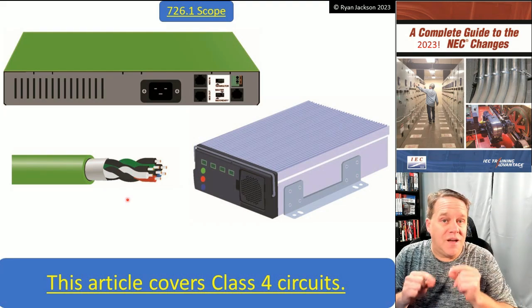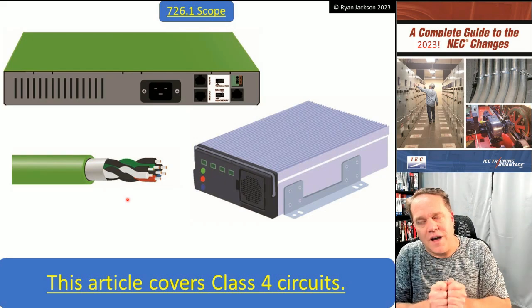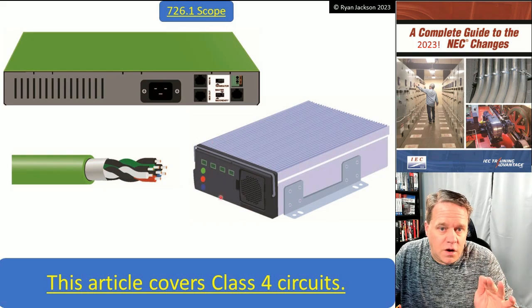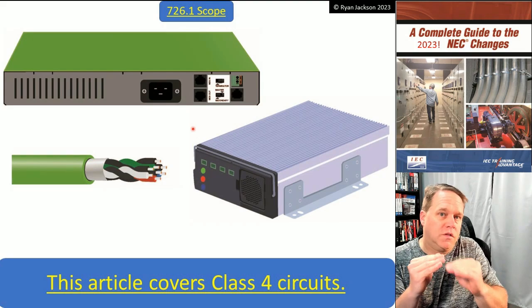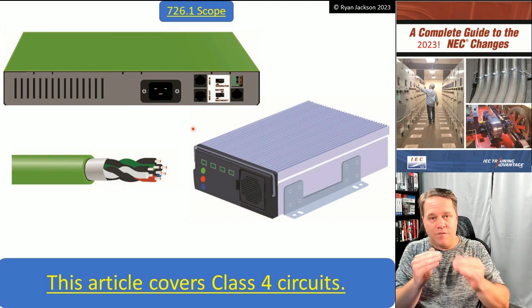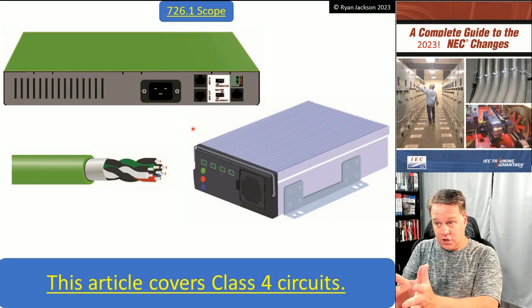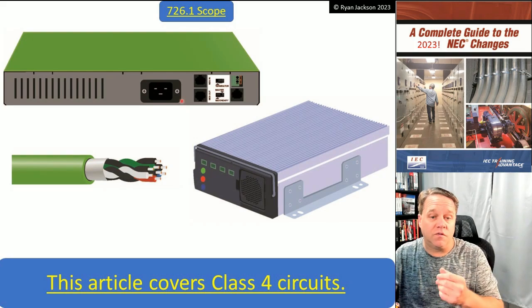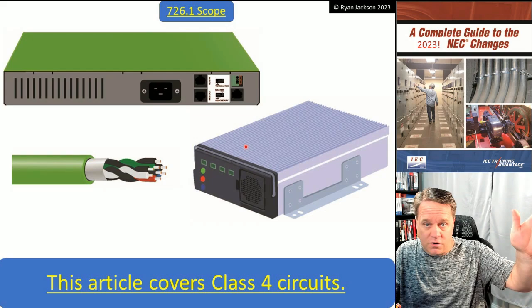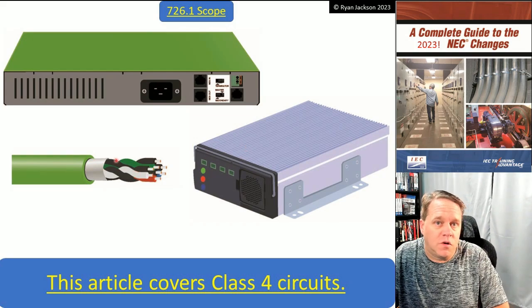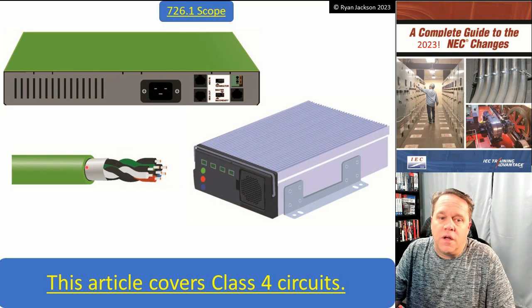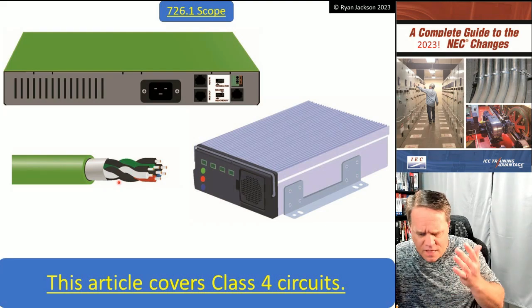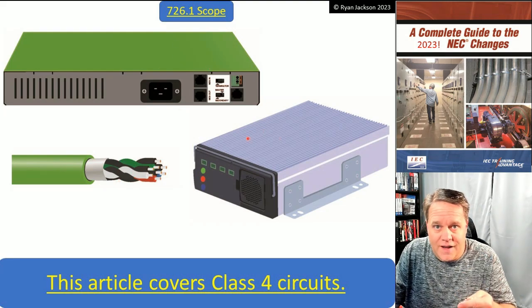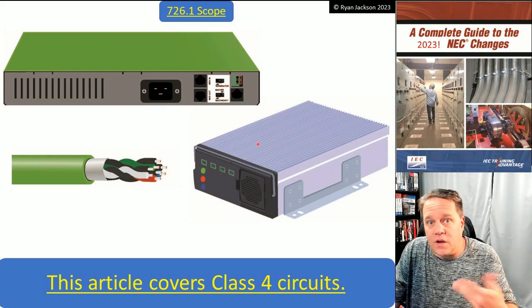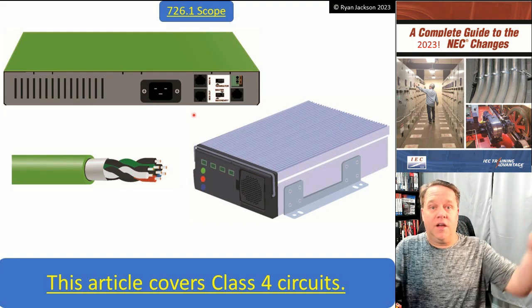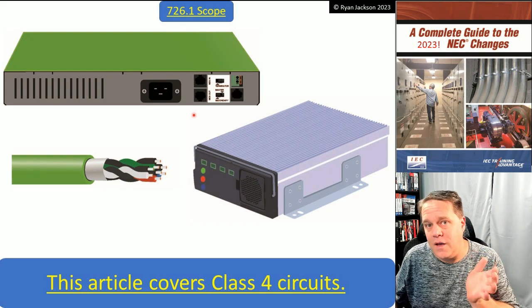So 500 times every second. Think about that for a minute. 500 times every second, the transmitter and the receiver communicate with each other, making sure that the circuit is still intact. So 500 times every second, the transmitter asks the receiver, hey, everything looking good? No breaks, no discontinuities, right? And the receiver is going to talk back to the transmitter and say, yep, loud and clear, we're good. If you were to have some sort of disruption, and by that I mean like a fault, so if you were to hit this wire with a hacksaw or something, well, the transmitter is going to ask the receiver if everything is good, and the receiver is not going to respond. So the transmitter is going to say, well, I guess not, and it shuts off. And it checks 500 times per second.